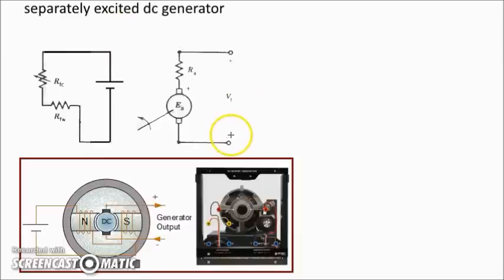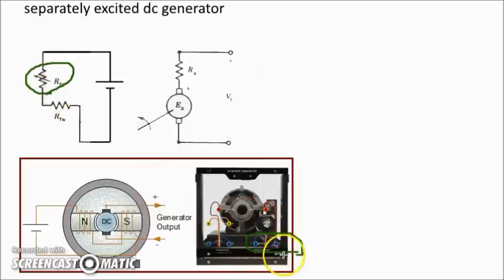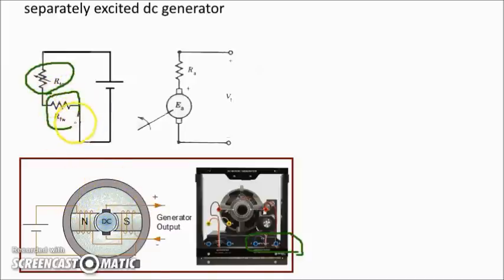On the top we can see the circuit diagram of this generator. RFC is the rheostat that you can see here. From the terminal of the machine we can change the resistance of the rheostat in order to control the amount of current that runs through the field winding. By changing field winding current, we can change the flux density inside the machine. RFW is the resistance of the field winding. For the armature, we have another resistance called Ra, which represents the resistance of the armature wires.